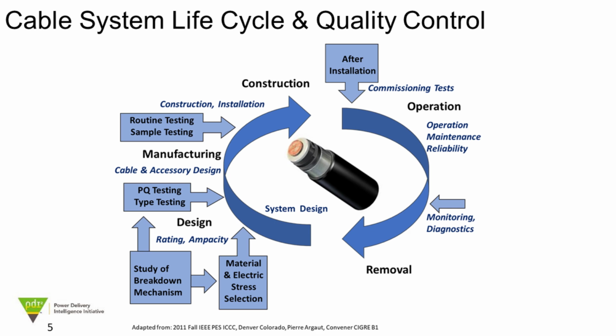Also there are materials that are aimed at particular conditions, for example tree retardant material or tree retardant cross-linked polyethylene, which is geared for medium voltage because of its susceptibility to being in water, to reduce the water tree formation in the cable. Higher voltage uses super smooth shields, insulation and conductor shields, as the voltage goes higher.